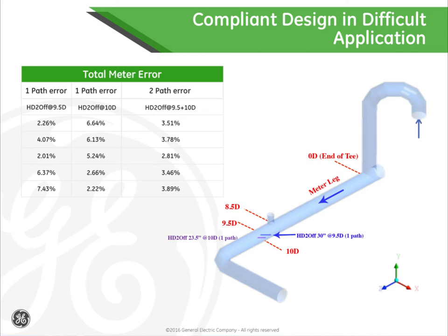Through computational fluid dynamic analysis, which Randy will discuss further in the next section, and proper meter design, we were able to provide them with a flare meter capable of measuring across this wide range of gas composition that can achieve the accuracy requirements of the regulatory body governing this flare, as seen in the accuracy table here. The specific regulatory requirements governing each flare are very critical in the design of the meter.